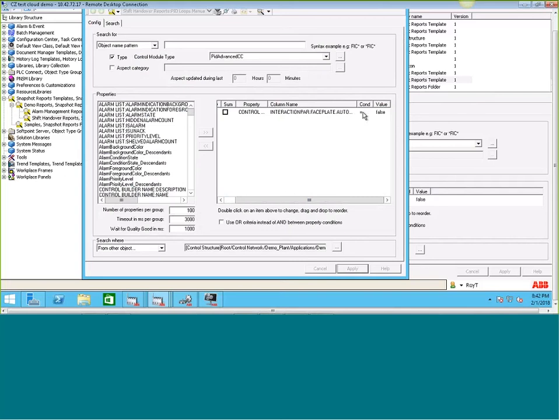And when you're configuring it, a little tip is when you click this, that's when you get the different operations that you want to use. This particular one looks at the PID Advanced CC. Now let's say you use the other PID, like PID Simple or something. You probably want to create another one of these, and then maybe put both of those in, because maybe somebody's used both object types. So again, this is going to go out and look for these particular object types.